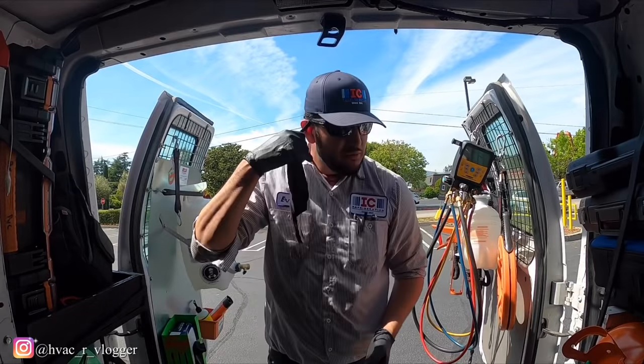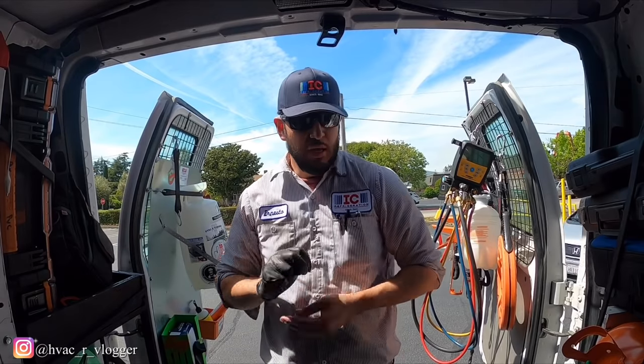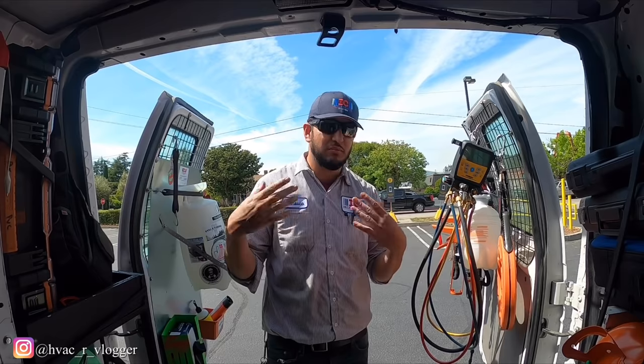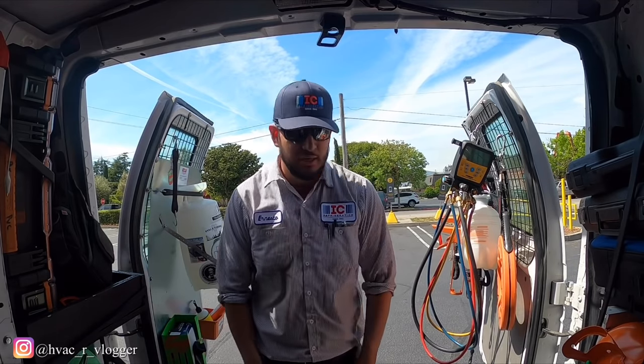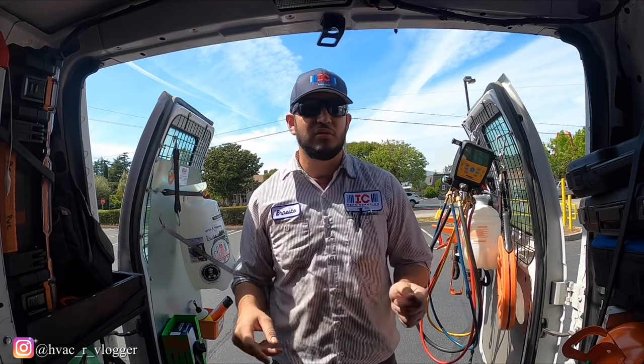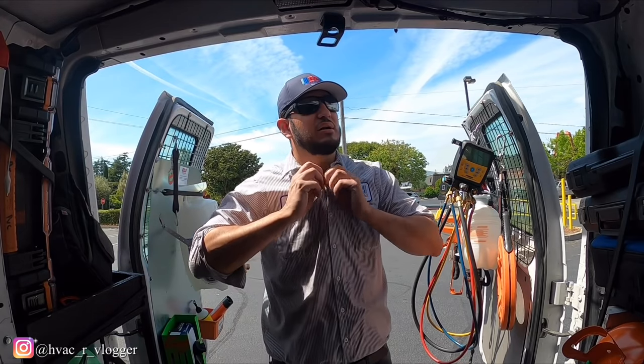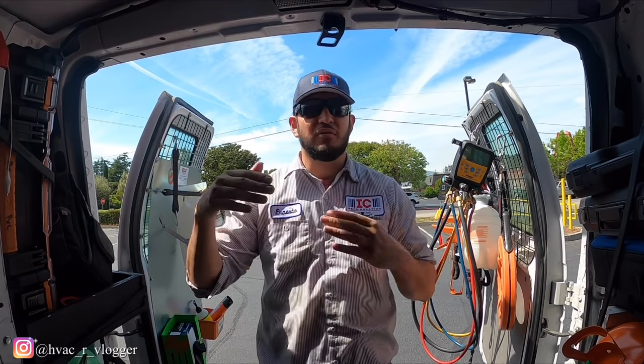That was pretty easy. I couldn't really talk inside that store, but basically what's going on, when I got there, the unit was completely off. Nothing was on, not even water, compressor, condenser, nothing. Once our manager opened up the bin and then closed it down, the unit kicked on. So right away I knew what the issue was. Those kind of ice machines have a bin control, and we call it the flapper.